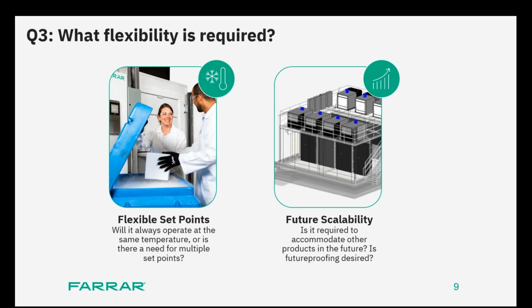Now, the conventional system or existing solution, Rebecca, what people can do right now is with those 20 freezers, you have to have 2 or 3 different set points. But imagine that initially you could just store all of your samples at -70. And then once the products are ready, you can actually go back and reset that to +5. That way, you're eliminating the need to have multiple freezers from your fleet at different set point temperatures. That's the power of scalability.